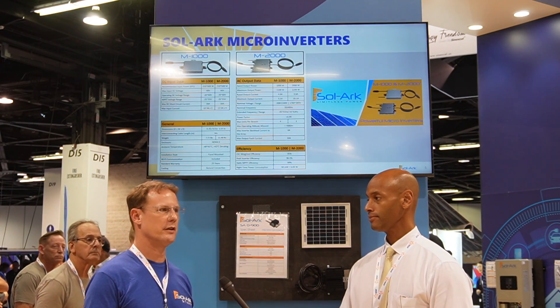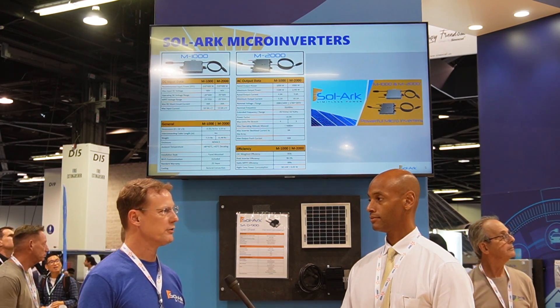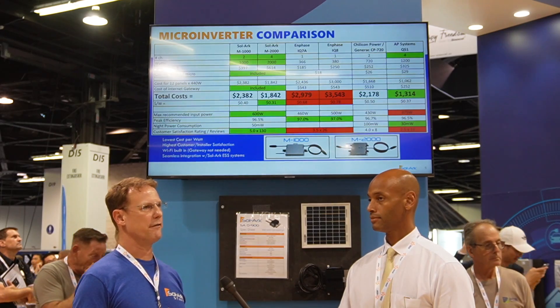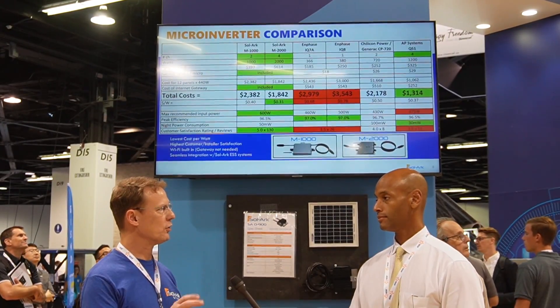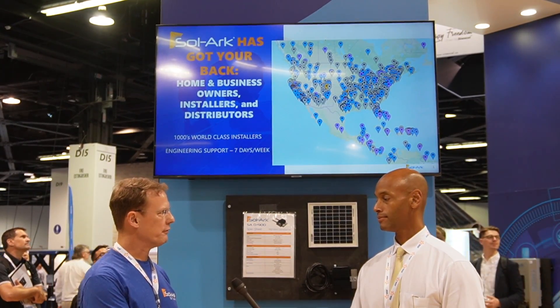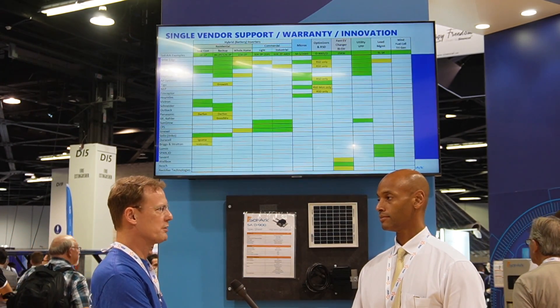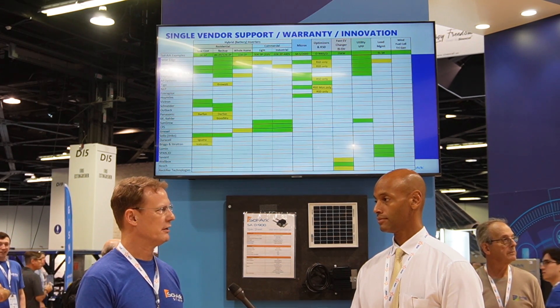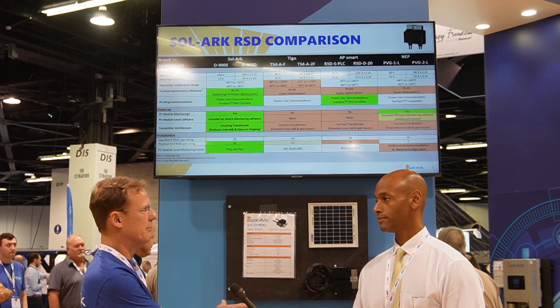The requirement for rapid shutdown was that you had to be able to hit a button — an emergency stop — and all the solar panels would stop producing power at each panel. It was a national requirement driven by firefighters, and it adds power electronics to every single solar panel. The advantage went to microinverters; it was actually written by some microinverter and DC optimizer companies to make string inverters more expensive. Rapid shutdown solves that, but it doesn't add monitoring or optimization.